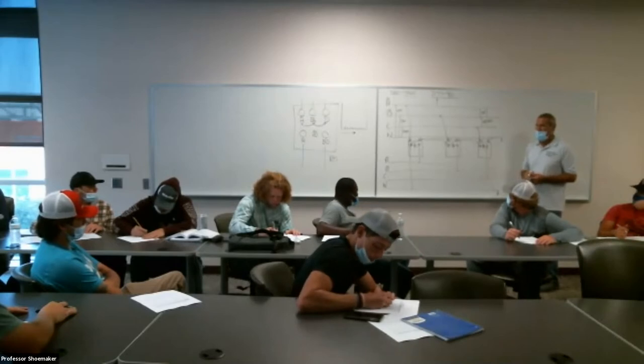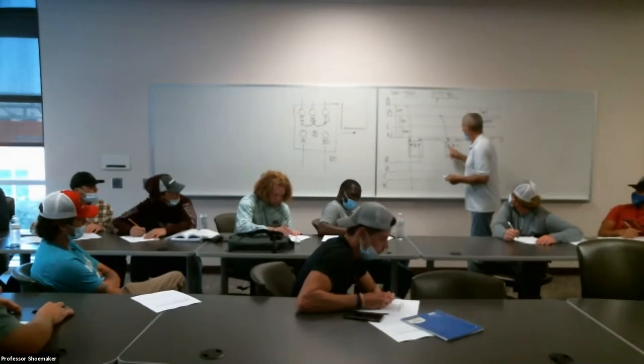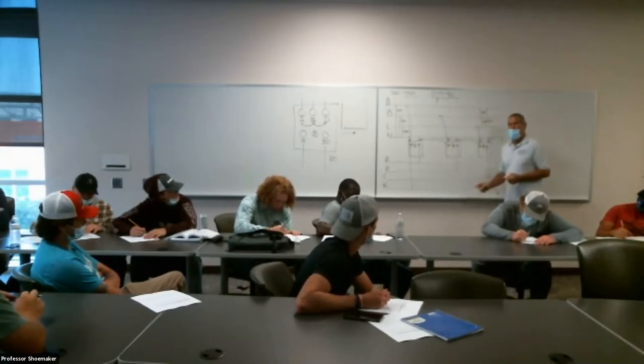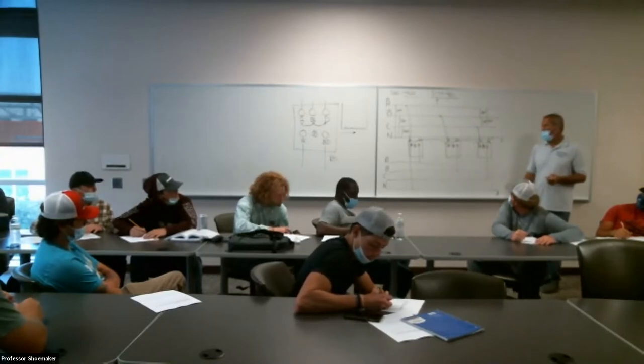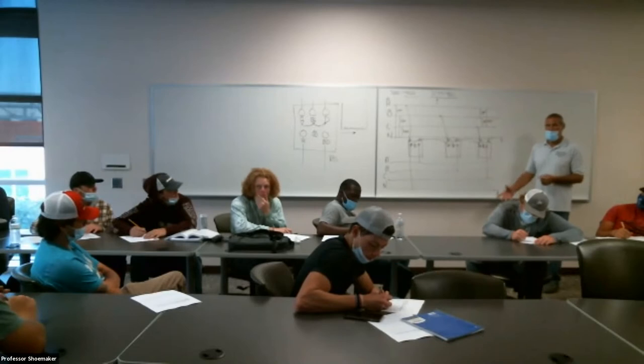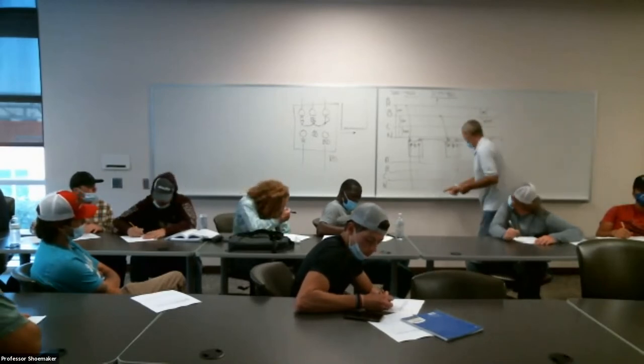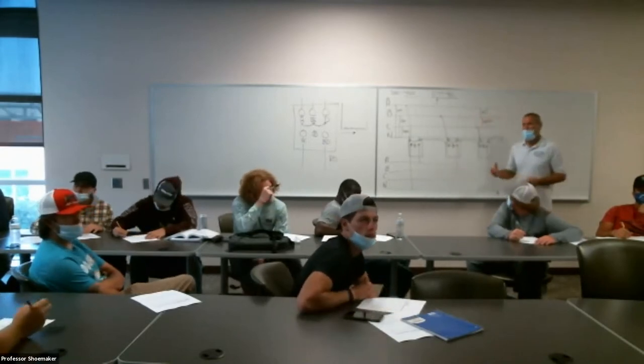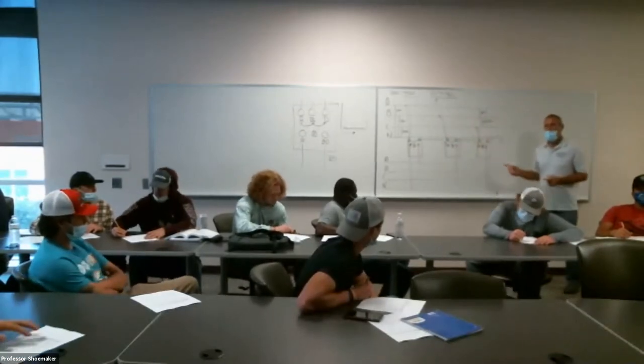Let me ask you this. Can I take a wire and go from here to neutral? Here to neutral and here to neutral. Yeah, but and not have to use the tie-in bus? Yeah, why? It's a waste of wire. It's a ton of connections you're gonna have done. Well, I've got one, two, three connections where I only have to make one here and then the transformers themselves interconnect.